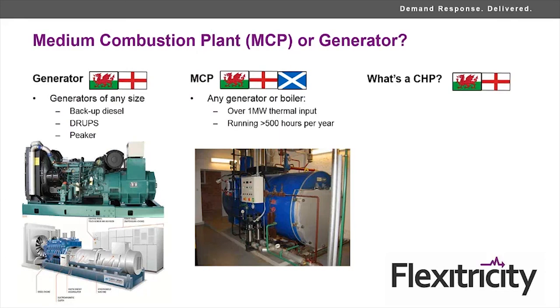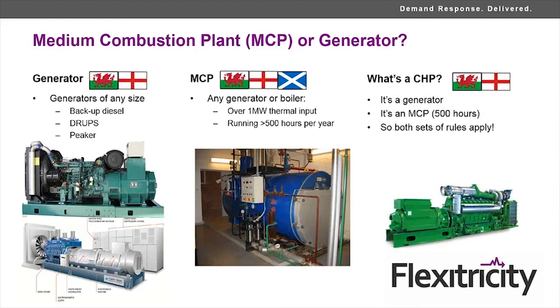So a CHP, what's a CHP? Well, a CHP is probably a generator and an MCP. It's a generator because it turns fuel into electricity, and it's an MCP because it's running over 500 hours. In most cases, it's likely to have more than 1 megawatt of thermal input, which corresponds to about 350-400 kilowatts of electrical output, meaning both sets of rules apply if it's in England and Wales.